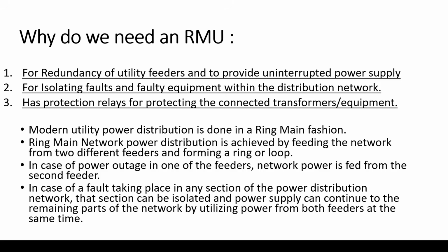The third reason is that RMUs have protection relays for protecting the connected transformers and equipment. As we have shown briefly earlier, the RMU outgoing usually has all the protective relays and functionalities to isolate or disconnect the downstream transformers in case of any fault, or any reason that might cause damage to the transformer. Therefore, I am providing an additional layer of protection to my transformers from the incoming distribution network.